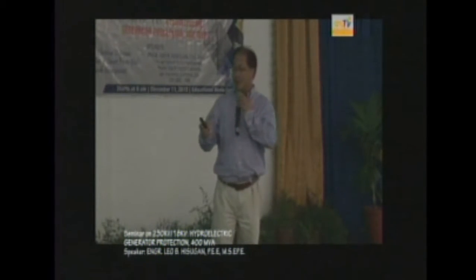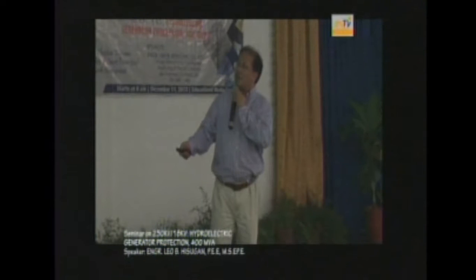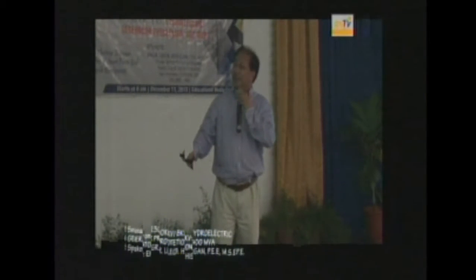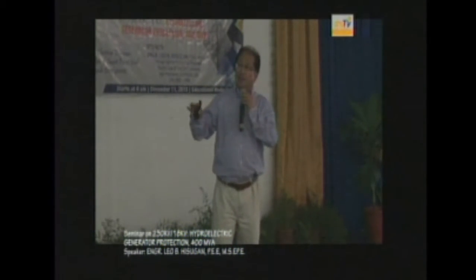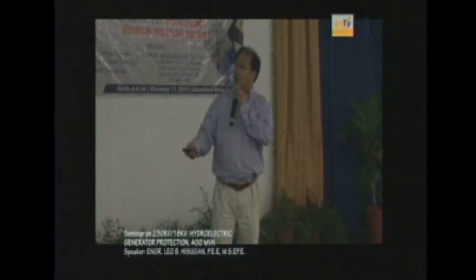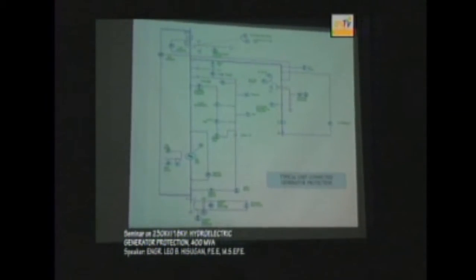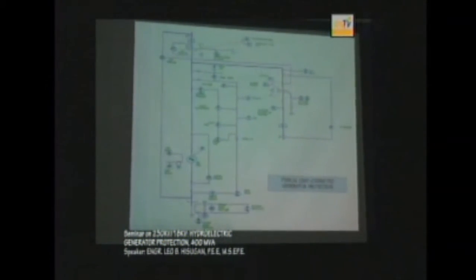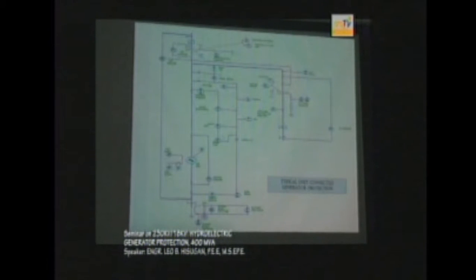High impedance grounding is when the impedance across here is very high, and the low impedance grounding is when the impedance on this primary side here is very low. The hybrid is a combination of both. We utilize the high impedance grounding for this generator because we would like to limit the short circuit current during a ground fault on the winding of the transformer to around 10 amps to 25 amps.